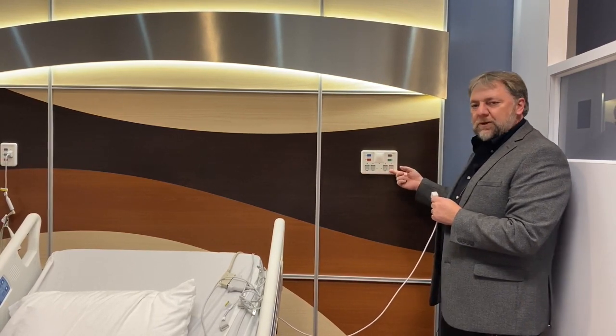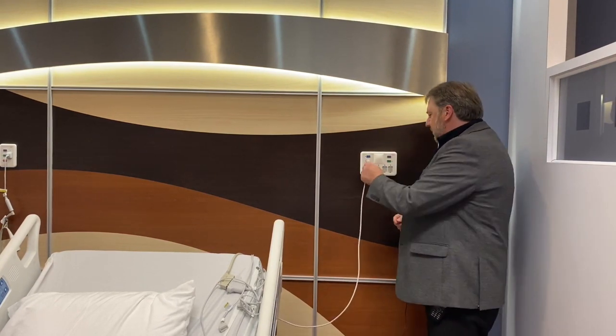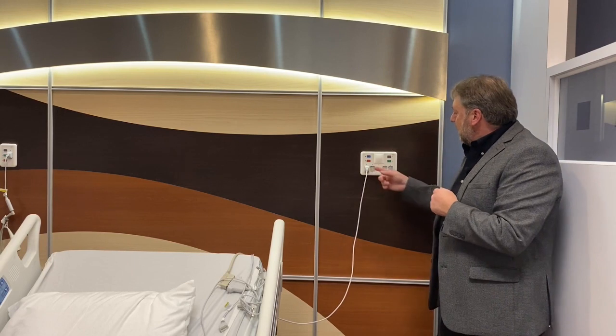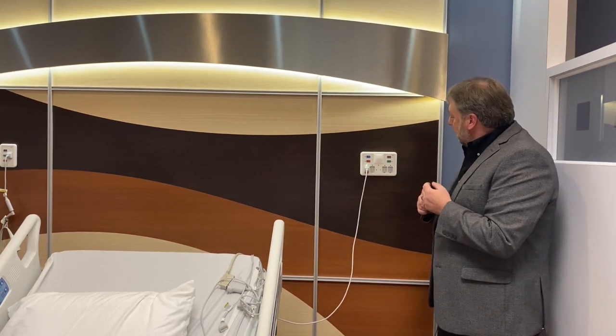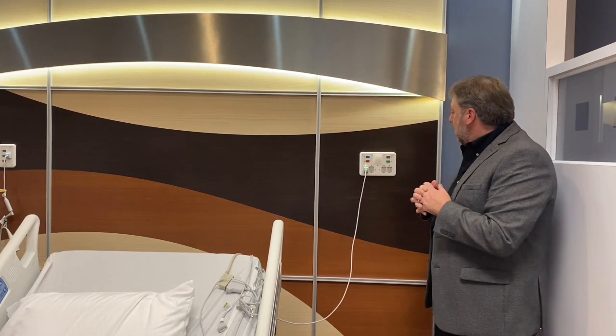We've got four what we call SafeConnect ports. This is a very unique feature. All of our call devices have a magnet and a staff member just has to get it close and it will plug in. The device will communicate — in this case it's a pillow speaker. We get the green light knowing that the station recognizes what has been plugged in and it's operational.